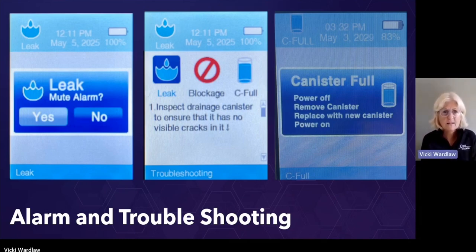In the center picture, you can see leak is highlighted, and then number 1 instructions: inspect drainage canister to ensure that it has no visible cracks in it. So that's an easy place to start if you have a leak. Notice there's a downward arrow at the end of that sentence telling you would use your down arrow to go to instructions number 2, number 3, number 4, and so forth. That is the same for the blockage alarm. Obviously, the instructions would be different, and it would be specific to a blockage. And then for your canister full alarm, the picture on the right is what will come up, and then also more detailed instructions on how to change the canister. But as I showed you, it's very simple.